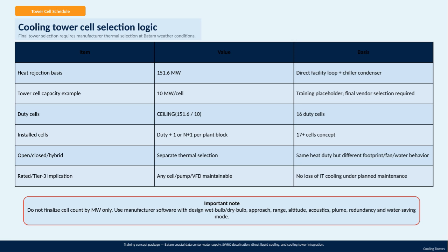Looking at the table, our heat rejection basis is 151.6 megawatts, which combines the direct facility loop and the chiller condenser load. We've estimated an example tower cell capacity at 10 megawatts per cell as a placeholder for training purposes. Dividing the total heat rejection by the cell capacity gives us 16 duty cells. However, to build in redundancy and ensure reliability, the installed cells will be duty cells plus an additional 1 or more, following an N+1 configuration per plant block, so about 17 or more cells.